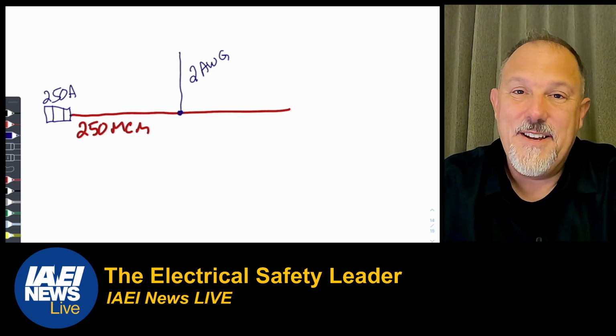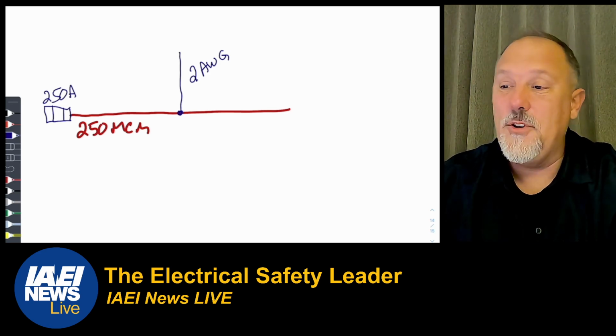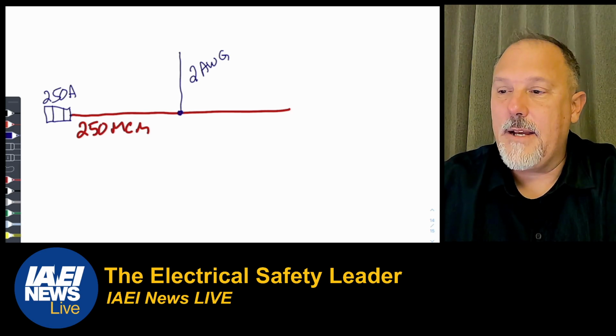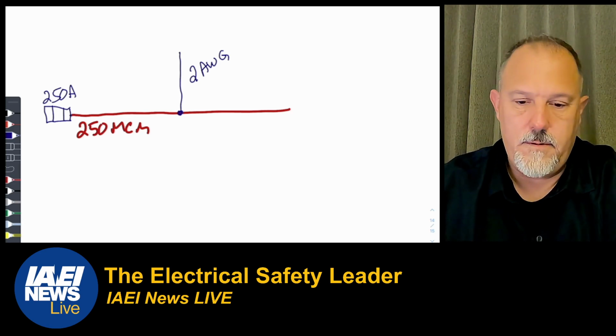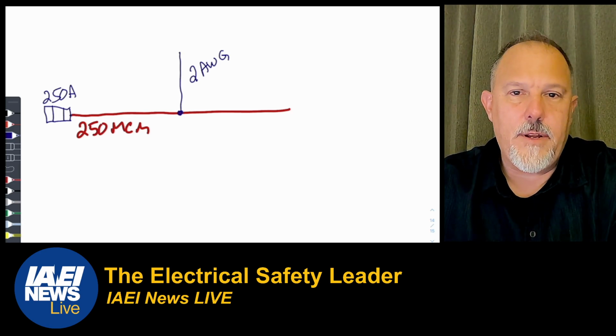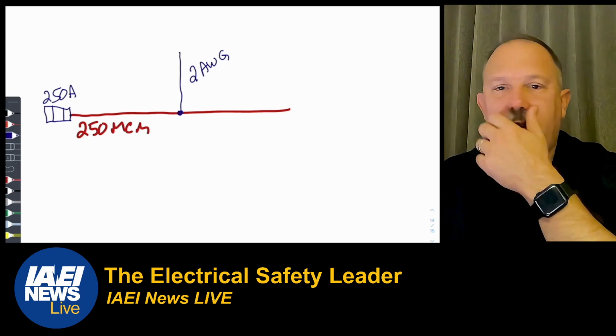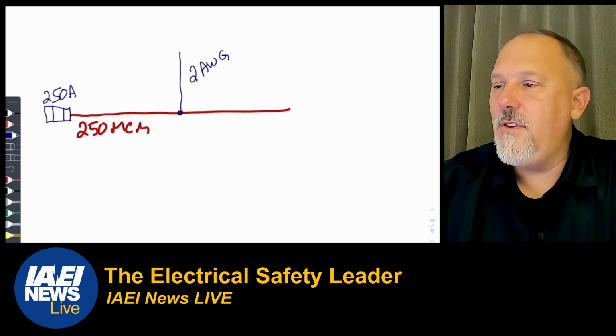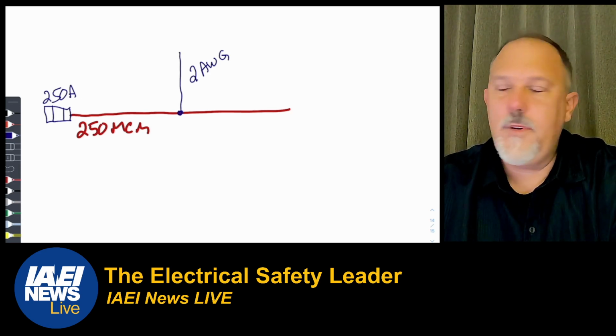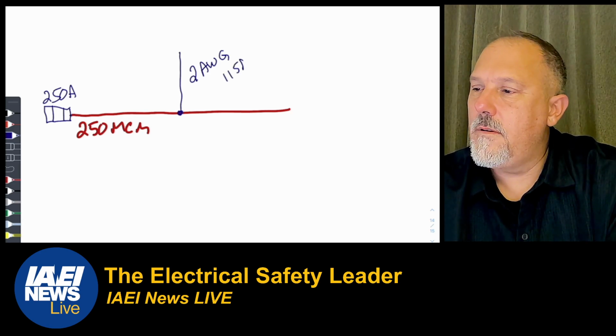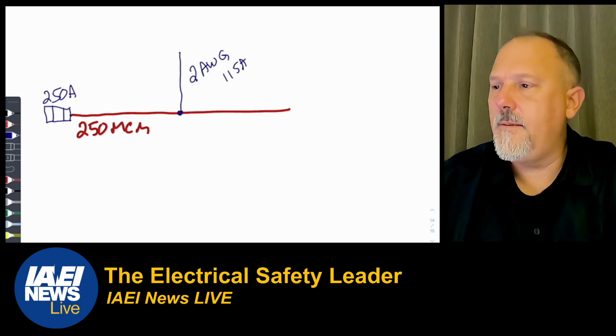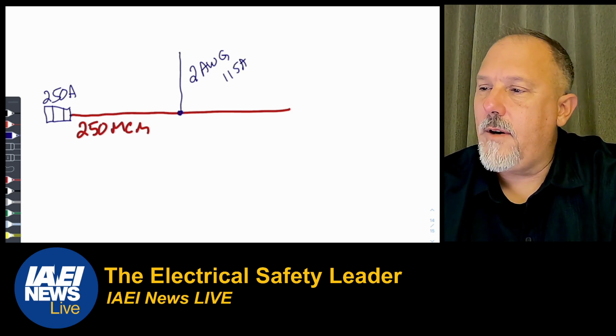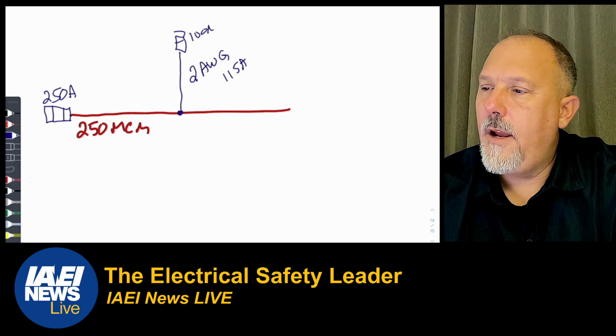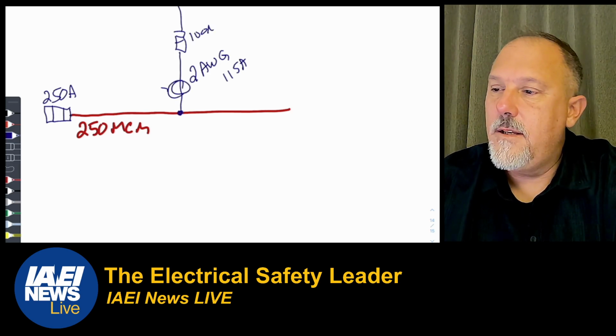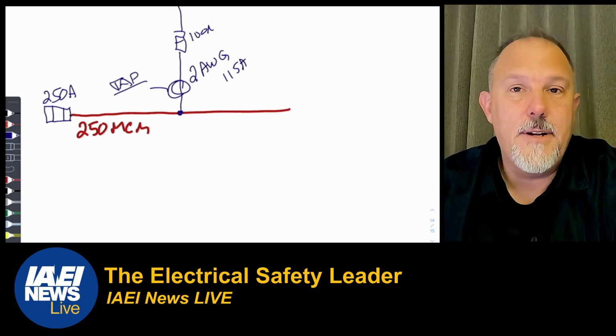Because remember, we're still in the phase of, hey, the 400 ain't cutting it. So you have to protect this conductor at its ampacity, and I believe that's 250. I can't remember the ampacity. 250 MCM, 255 amps. So a 250 amp fuse. So I put a 250 amp fuse, but a number 2 is around 115 amps, if I'm not mistaken. Yep, 115 amps. And I have a 100 amp, and then I go out, right? So this is a tap conductor, and it's not.